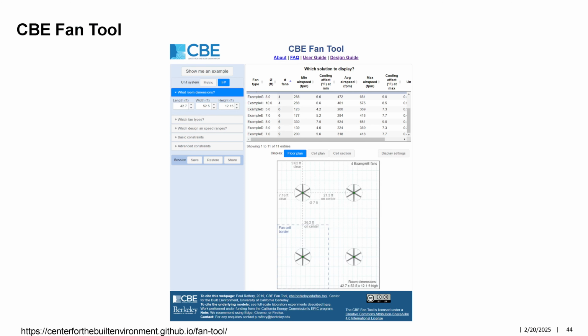The second tool is the CBE fan tool, and this tool allows you to figure out how many ceiling fans you would need in the space and estimate the expected airflow speeds in the space. And it supports various types of fans with a variety of different specifications. It's useful when you're trying to design a radiant and ceiling fan coupled system, but it's also useful to use it with a normal conventional all-air system because, like I said earlier, the increased air movement also produces a cooling effect on people.